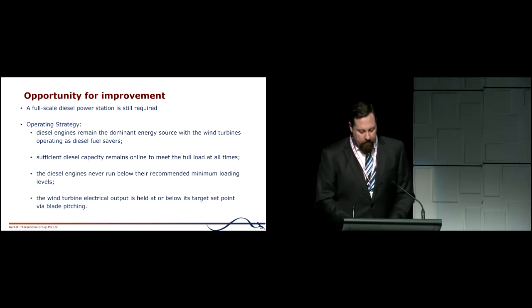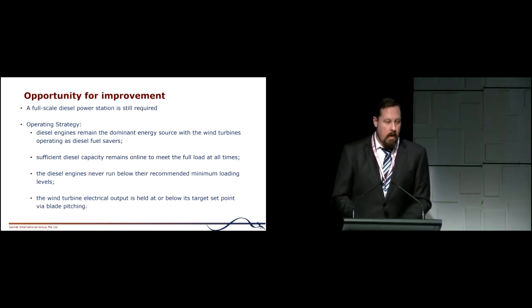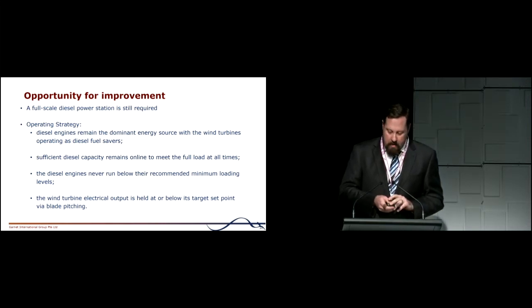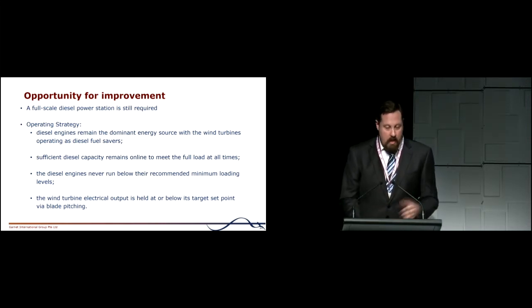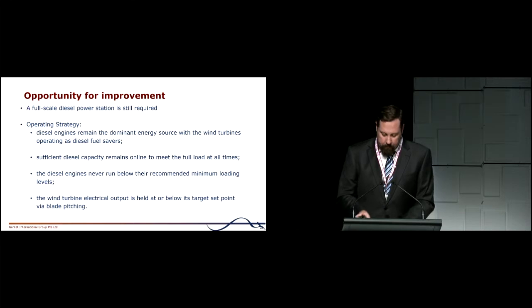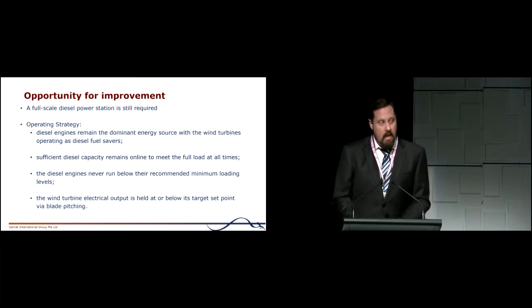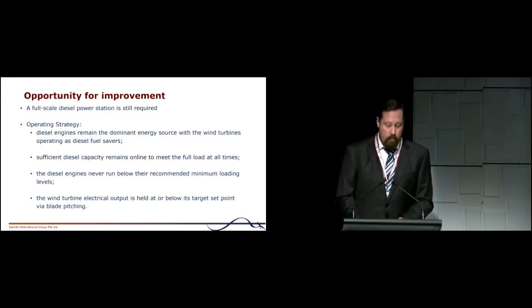The full-scale diesel power station is still required to operate the site. When the air is still and no power is generated, it reduces the risk of brownouts from changes in wind speed. Just to note, in our case the mineral sands mine doesn't have any exceptionally large electrical loads, such as crushers and ball mills - it's multitudes of pumps. So the power demands and profiles are different to other types of mines.